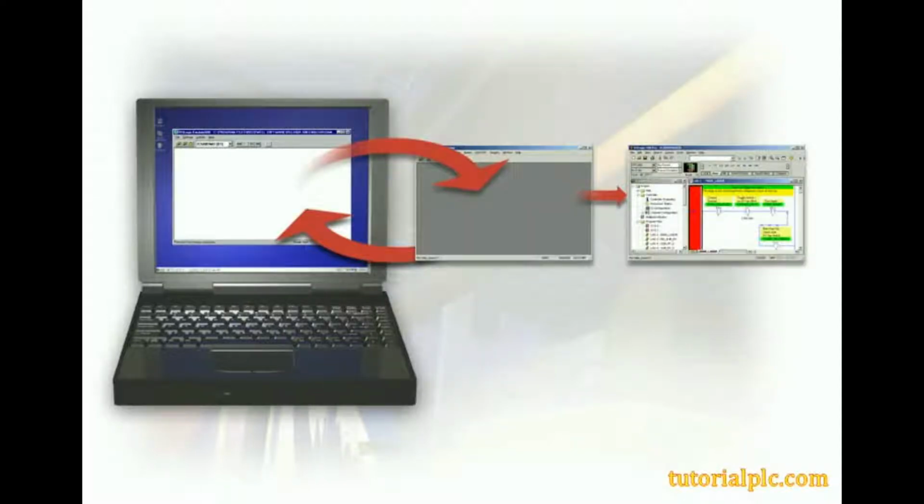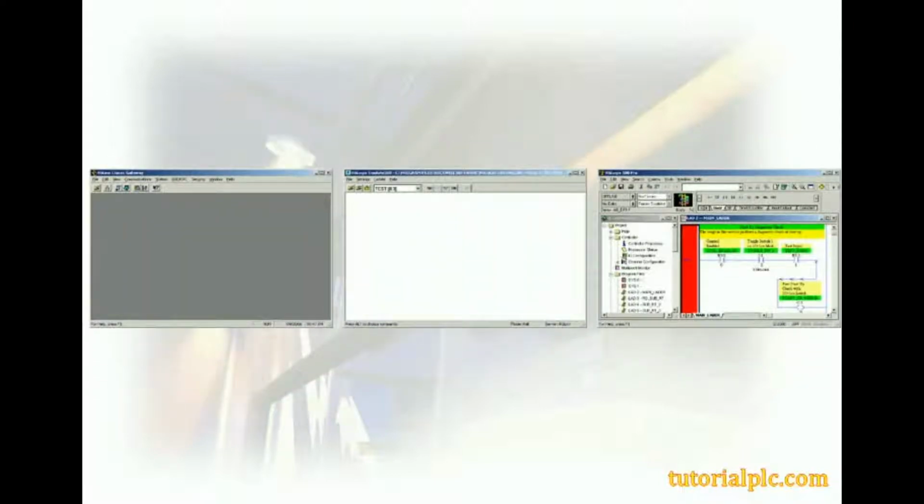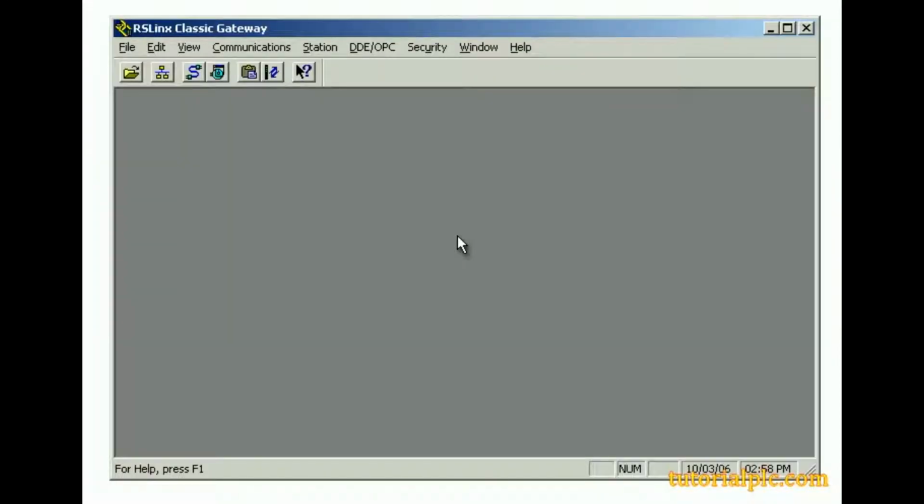We'll go online with RSLogix Emulate 500 software from a computer using RSLogix 500 software. Communication between these two applications is facilitated by an SLC 500 emulator driver, which we set up in RSLinx software. The most effective method of establishing communications is to configure RSLinx software first, followed by RSLogix Emulate 500 software, and then RSLogix 500 software. Before RSLogix Emulate 500 software and RSLogix 500 software can communicate, RSLinx software must be running and must have the proper communication driver set up and running.